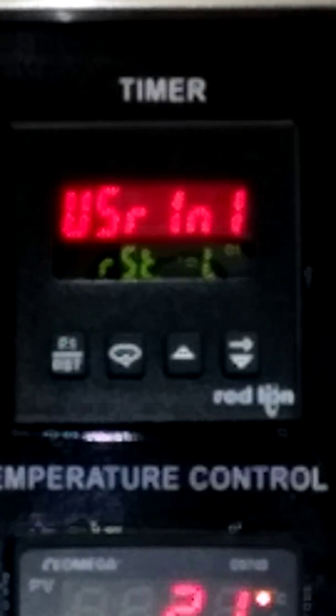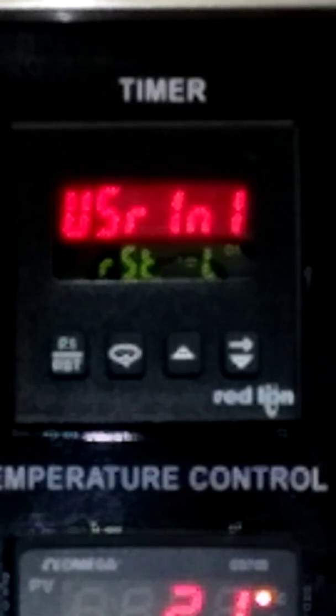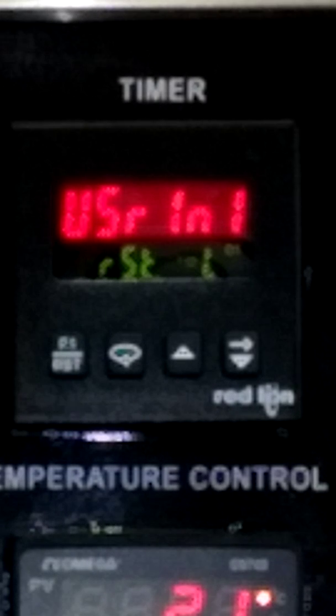User inputs: three external user inputs plus the front panel function key are available if you need more than one output. With the L setting, it's reset level active — when the user input is activated, the timer value and outputs will be reset and held reset until the user input is released.